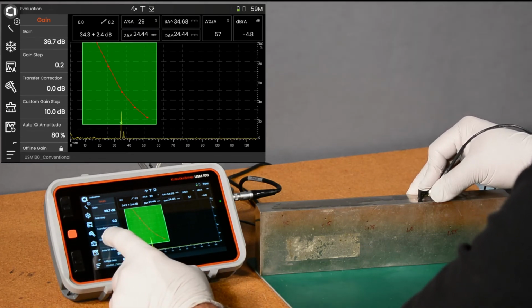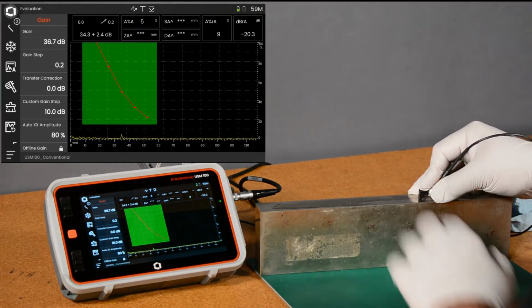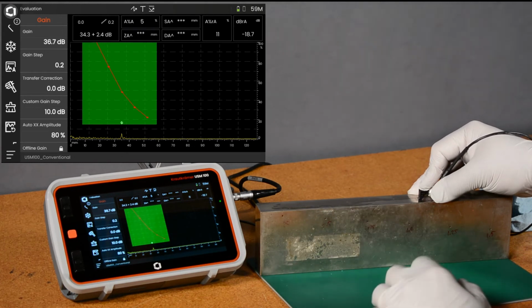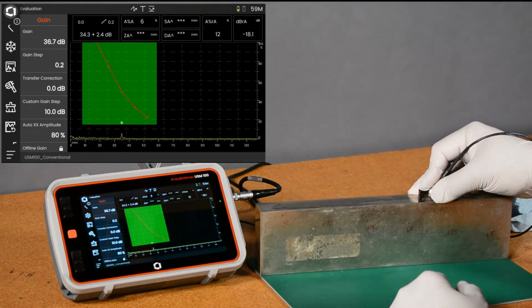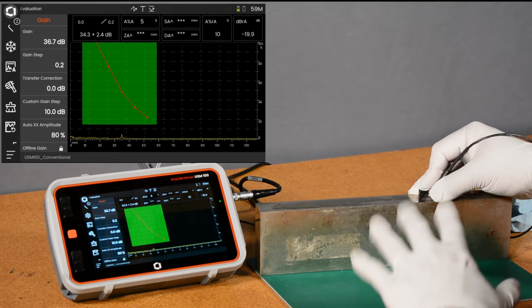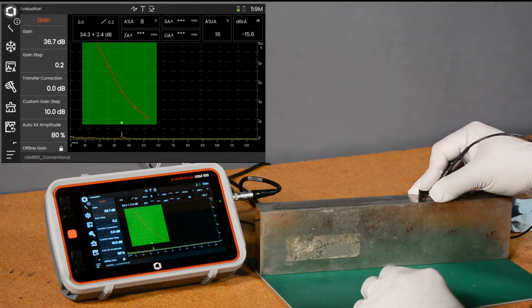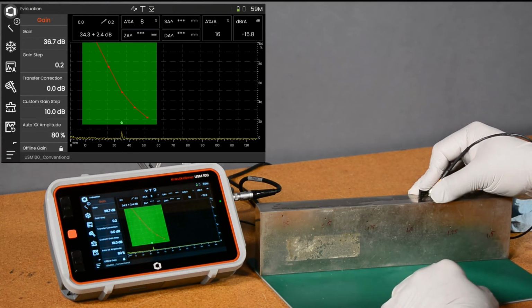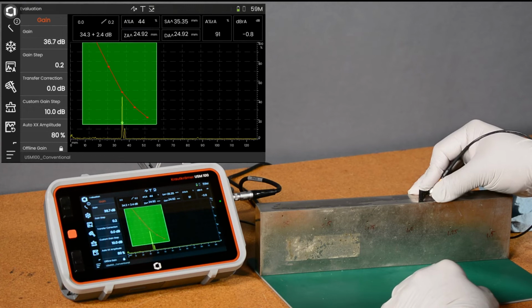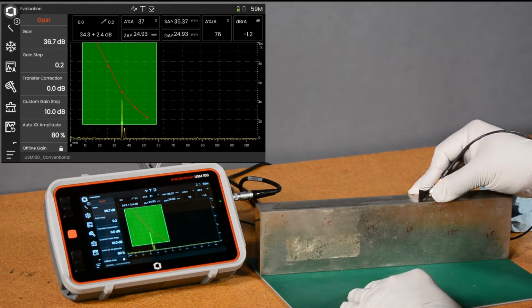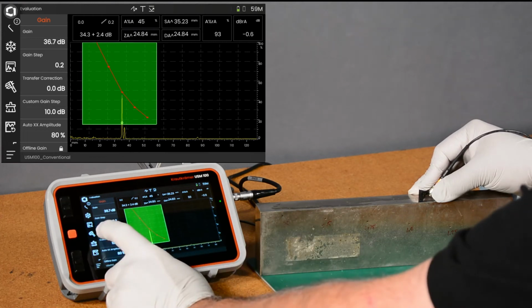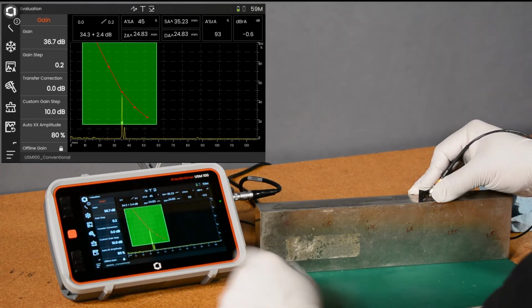We have a couple of controls on here that are useful. One is transfer correction. So we're setting up on a nice clean calibration block here. In the real world, I may have surface roughness and things like that to deal with on my sample, and I can apply transfer correction gain. I won't go into how that's all calculated. Generally it's done with a through shot with a matching probe to the one that you're using, and you can establish how much attenuation happens in getting the signal into and out of your block, or if the material that you're inspecting is more attenuative than your calibration block, different heat treat. Those are all reasons that you might want to apply transfer correction, and that's done here in the gain menu.